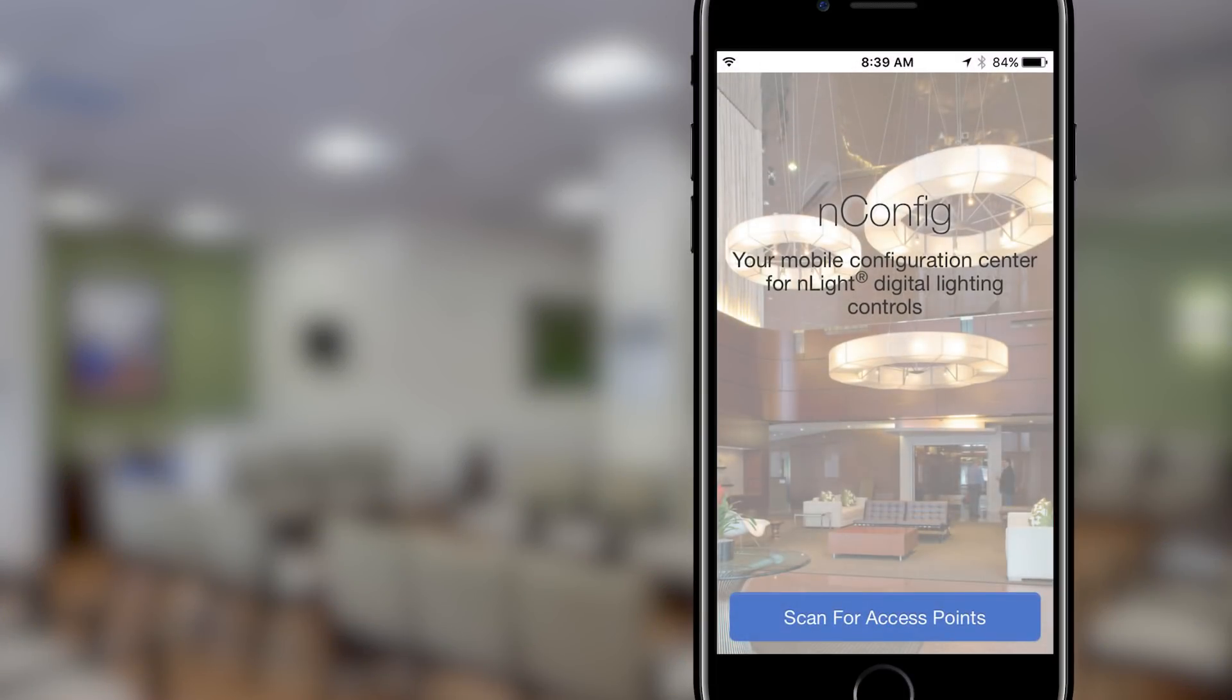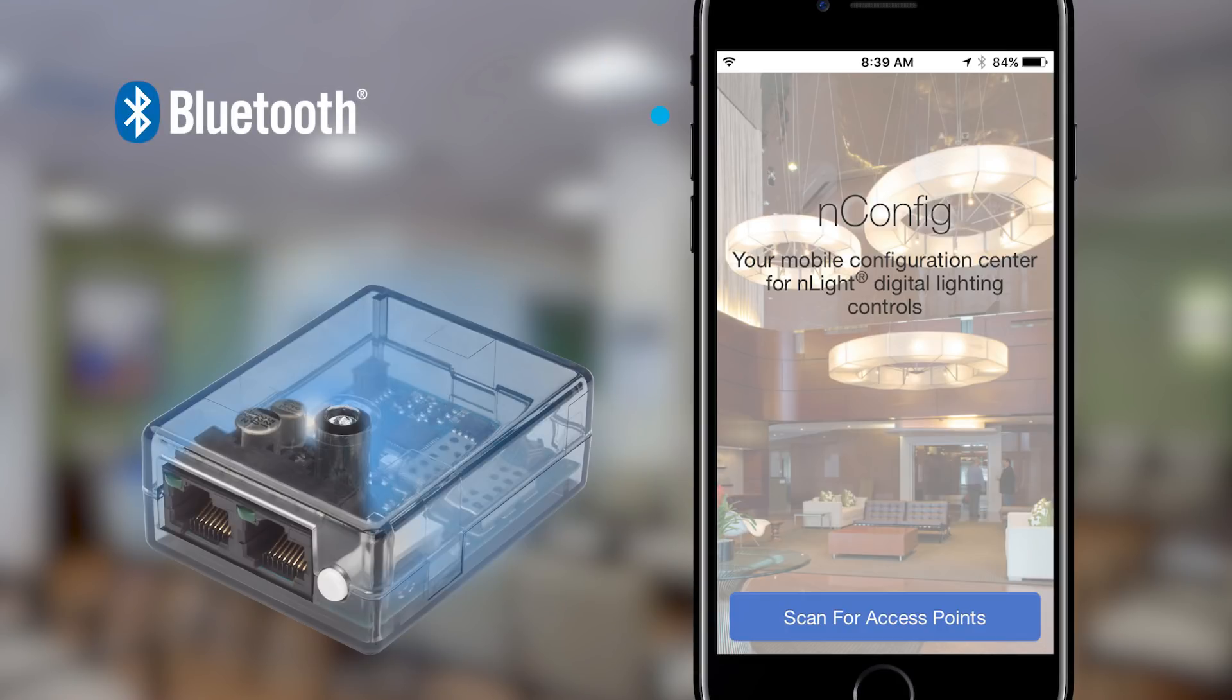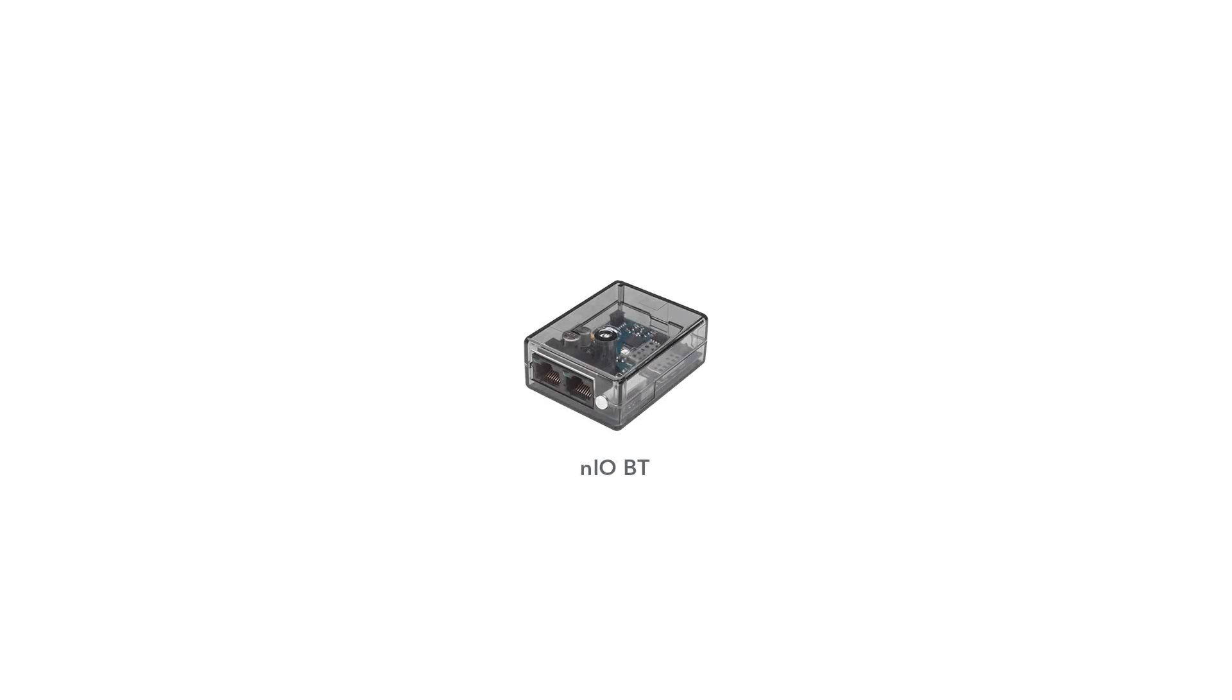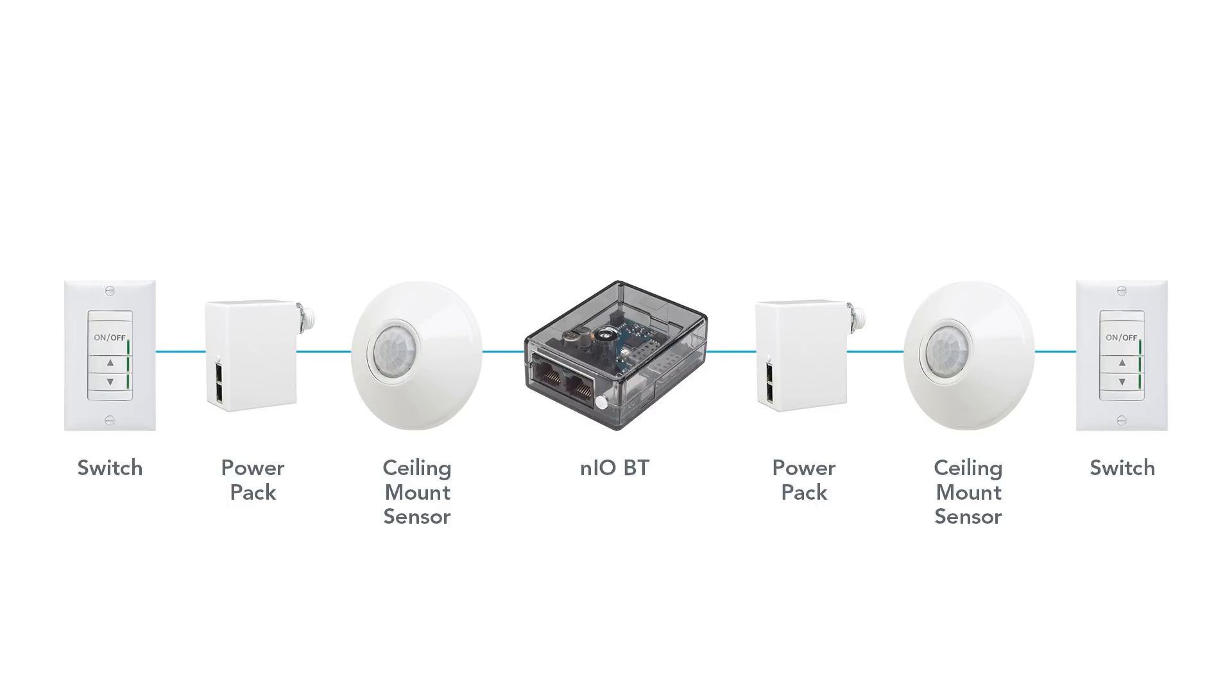For the nConfig app to work with your nLight equipment, a nIO BT must be part of the zone. The nIO BT translates the Bluetooth commands from your phone into nLight commands. The nIO BT can be added to any point within the nLight daisy chain and it powers off of the nLight low-voltage CAT5 bus. No additional wiring is necessary.